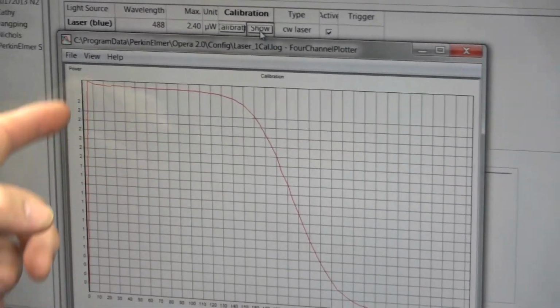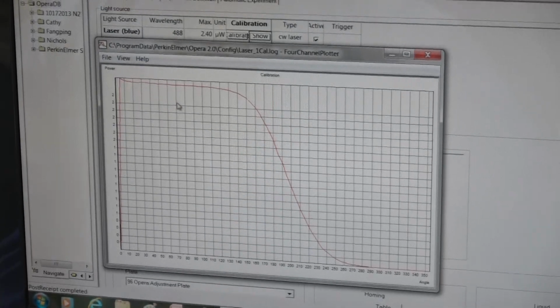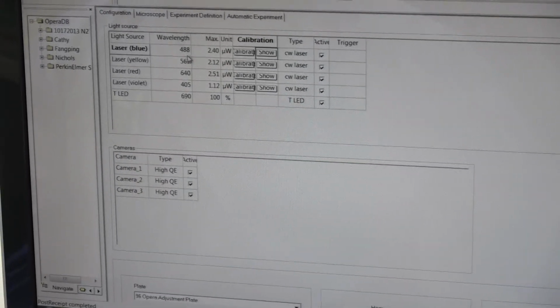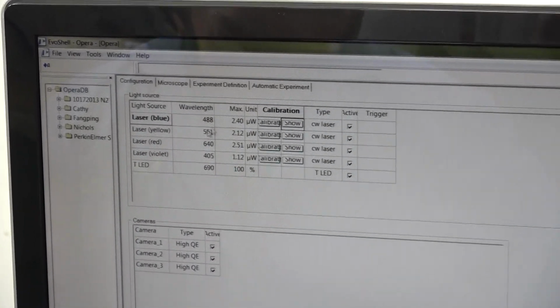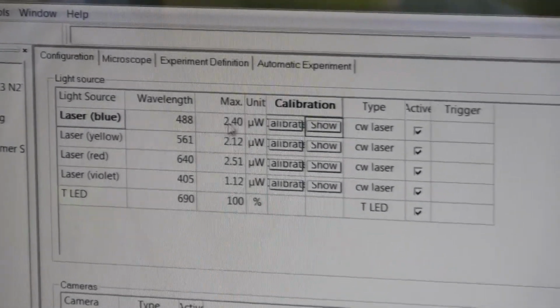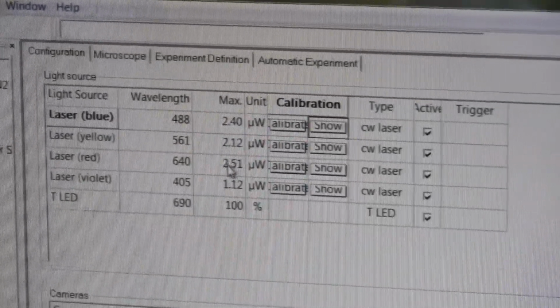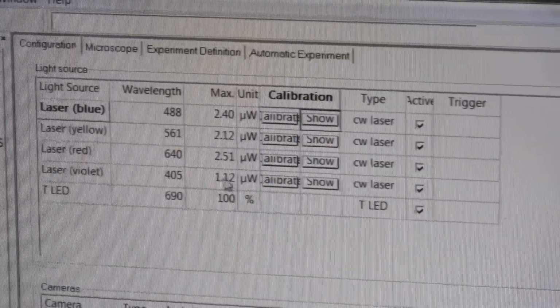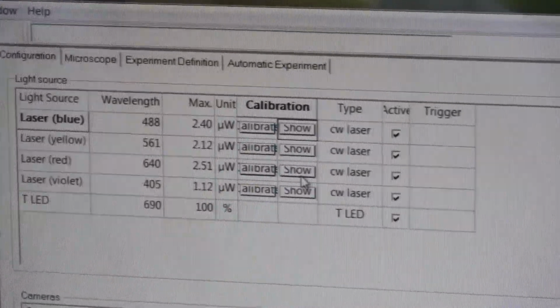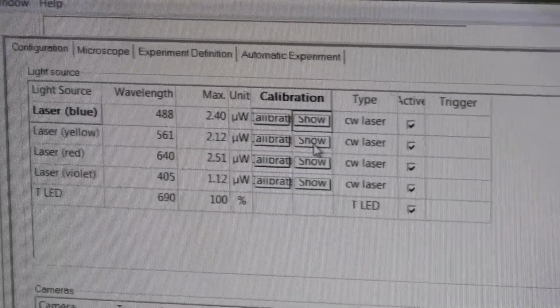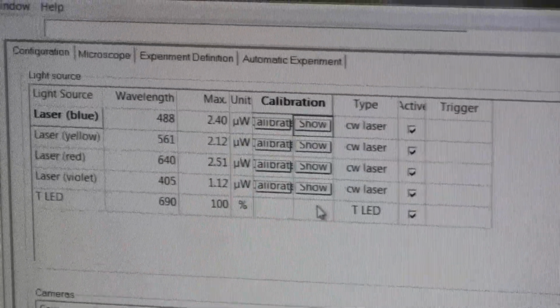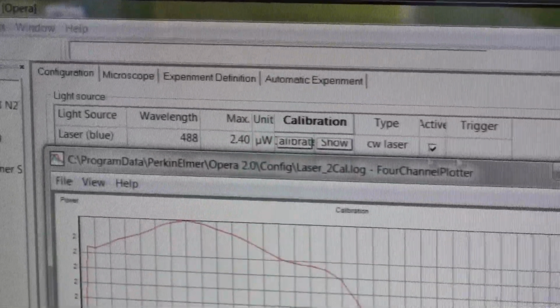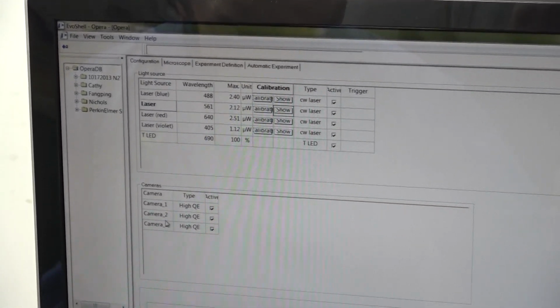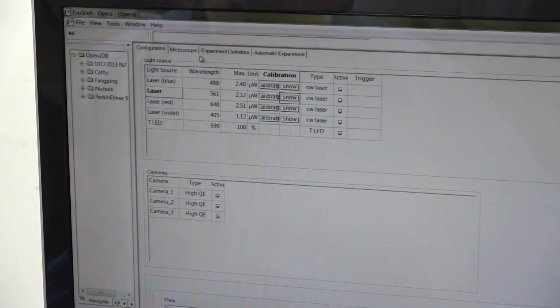This is the first laser, and it peaks out fine. But once they're calibrated, these numbers will go up extremely much higher. These numbers here will go up to more of a 5. This one will go up to more of a 3, and a 3 here, maybe a 2 here. But right now, like I said, until the machine is stabilized and ready to be used, it really doesn't make much sense to calibrate the lasers because they get jolted around again. But like I said, all of them are calibrating fine. Even with the cameras, once it's set up, aligning the cameras is something that would need to be done, and that's something that I offer also for the customers.